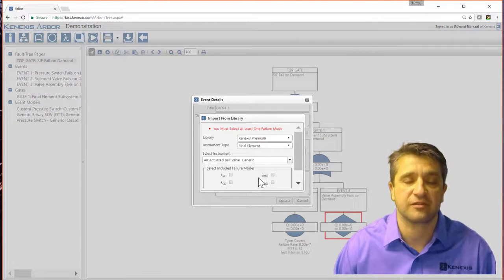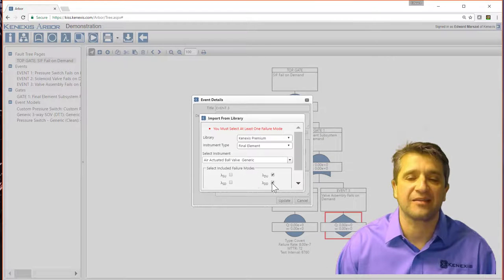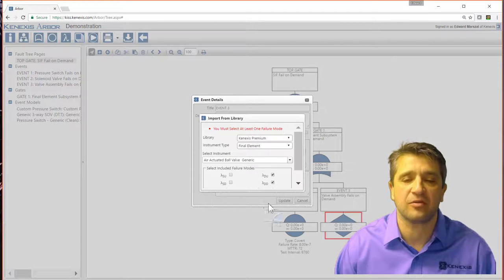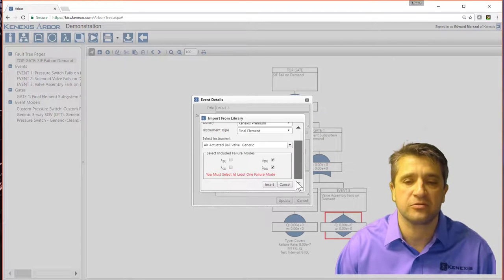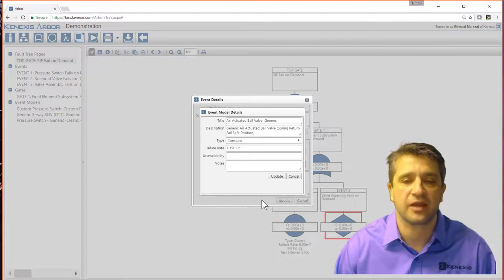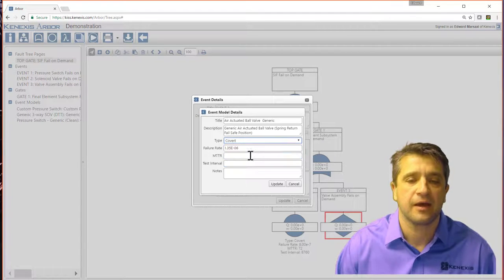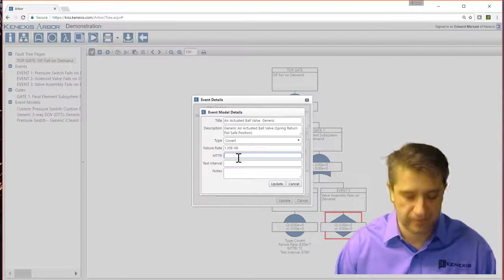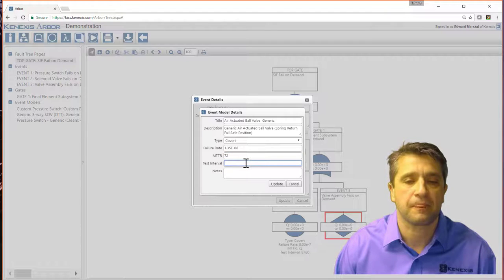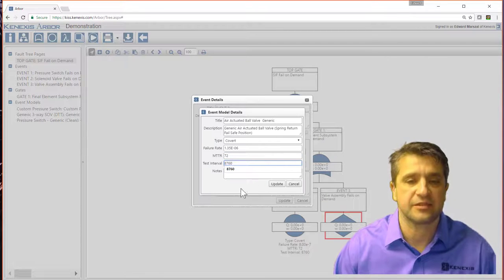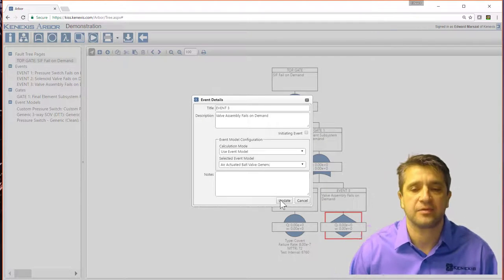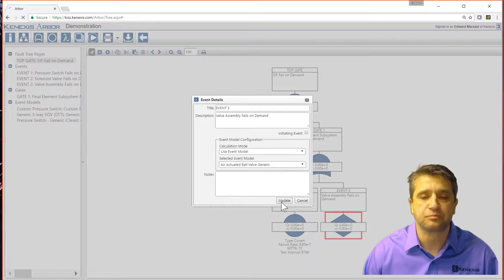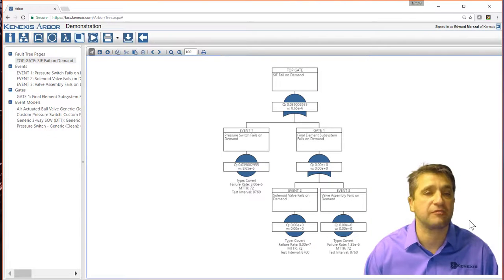I have to select the failure mode. So lambda DU, lambda DD, the dangerous failure modes. And hit insert. And now it created everything. So covert, 72, 8760. And hit update. And I have all the information.